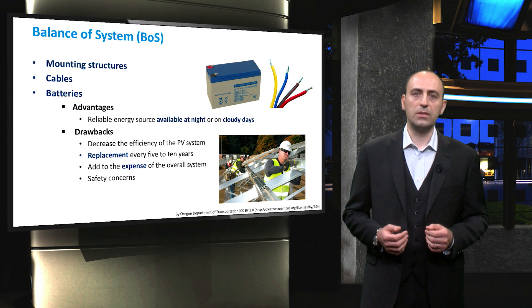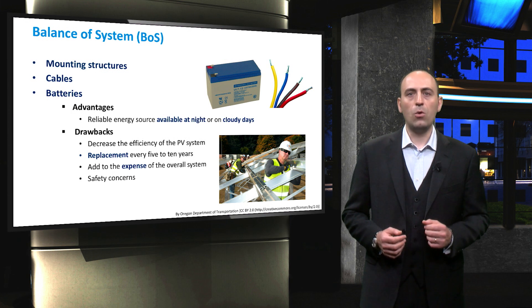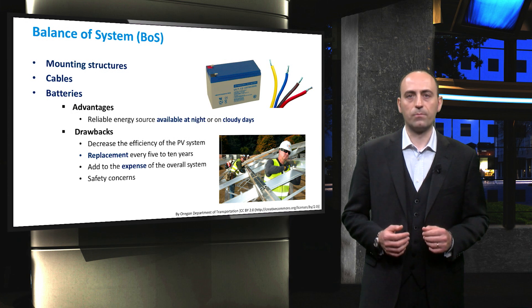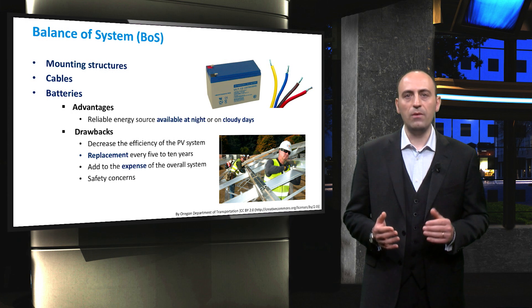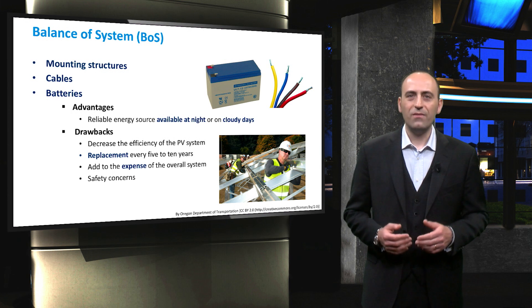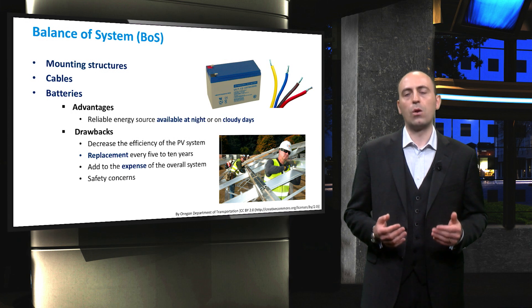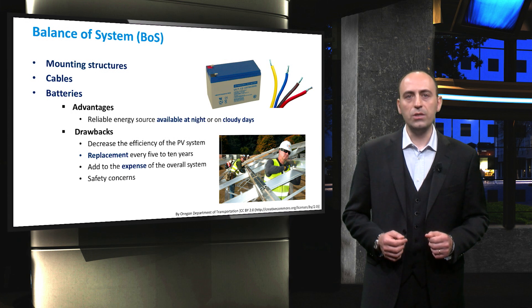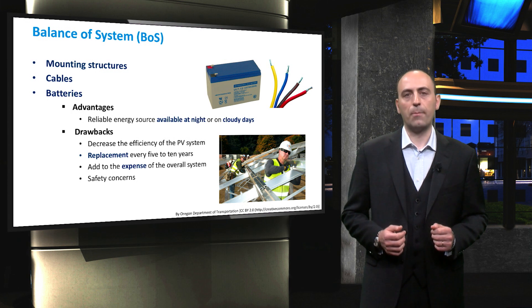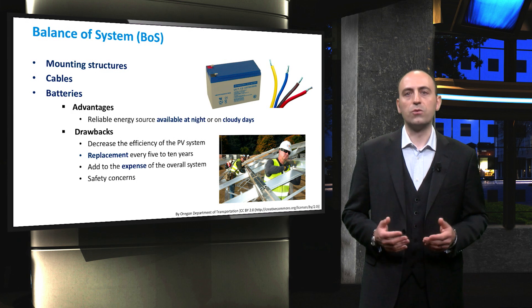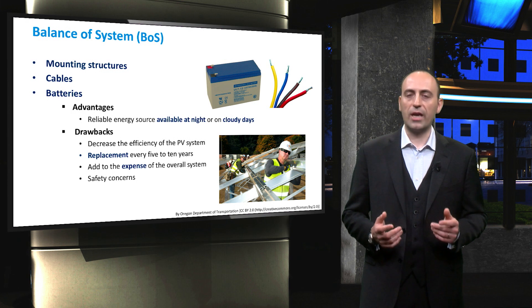So, when you want to have a PV system with storage, you have to take that into account. The PV modules are characterized by a certain lifetime, usually 25 warranted years. The batteries, however, have a much shorter lifetime of somewhere between 5 and 10 years. On the market, there are many types of batteries, but for PV applications, often lead acid batteries are used. They are somewhat similar to those used in cars, except for some special design considerations aimed to prolong lifetime. When you need a lightweight system or high storage capacity, the use of lithium-ion technology is preferable, but also more expensive. Lastly, it is also important to account for safety regarding thermal control and health concerns on the chemistry employed.